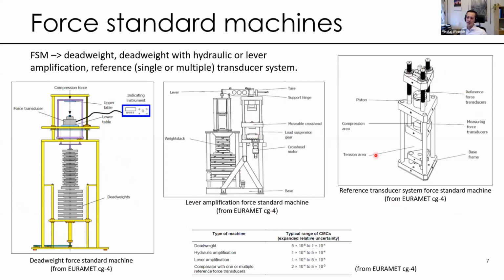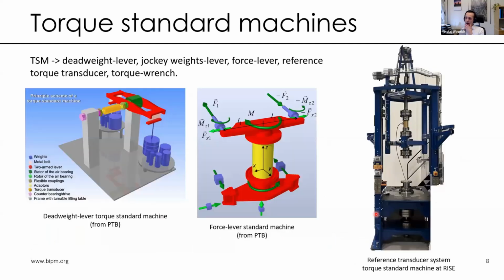In the case of secondary systems, we can have a reference transducer consisting of single or multiple transducers. And typical values for these different types of machines are provided here. All these images are taken from a Euramet guide, a calibration guide available on the Euramet website. In case of torque, the principles are similar. Of course, they differ because it's a slightly different quantity. They both are related, but of course the realization is different. So for the pure primary systems, we use deadweight lever machines, where we use weights as well in the gravitational field, as well as a lever system.